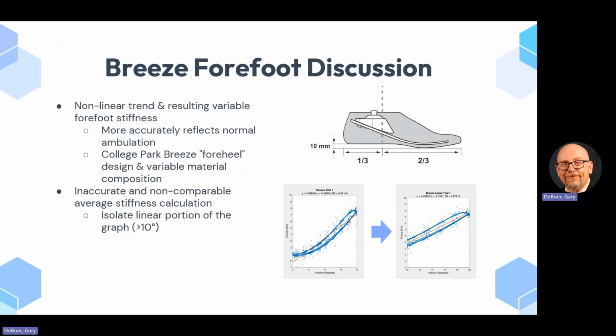But that nonlinear trend and then the resulting nonlinear graph is actually what we would expect from normal ambulation, which is what the College Park flexible keel foot is trying to simulate because of this foreheel shape, is what they call it. So going from the forefoot to the heel, it's composed of this composite material structure, and that shape is trying to mimic normal ambulation. So during normal ambulation, the metatarsal phalangeal joint, which is really just like the ball of your foot, actually absorbs energy and increases in stiffness when it's getting dorsiflexed during terminal stance to help you prepare for push-off and propulsion forward during swing phase.